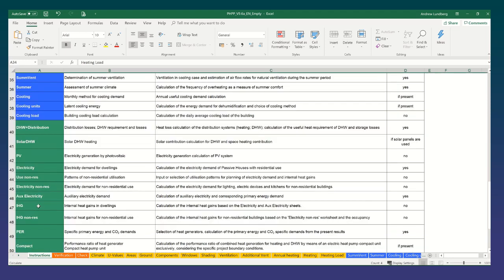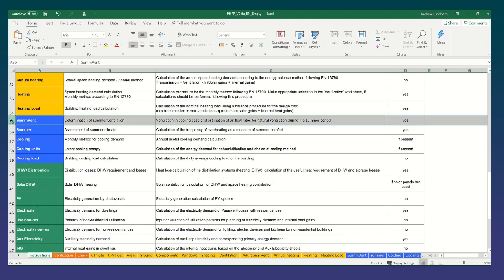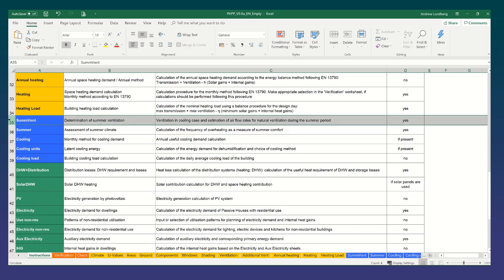Moving on then from the building fabric section we then have a few tabs that calculate the effect of summer ventilation so you can use this to calculate how much ventilation is required in summer be it mechanical or natural opening of windows, the heat recovery system on in summer bypass so therefore not actually using heat recovery but with automatically controlled summer bypass or manual bypass, or with active cooling you can calculate as well what the actual cooling load and demand is for the building for sizing cooling plant and then you can determine the effect of that on the overheating risk in the building. So there isn't a lot to input on the summer sheets it's more for calculating the overheating risk but a lot of the parameters that affect the summer overheating level are in the building fabric section to do with for example orientation, extent of glazing, g values on the glazing and other items such as that.